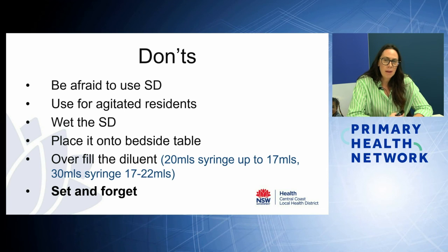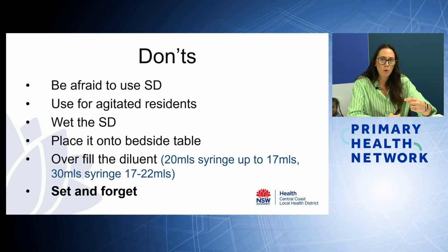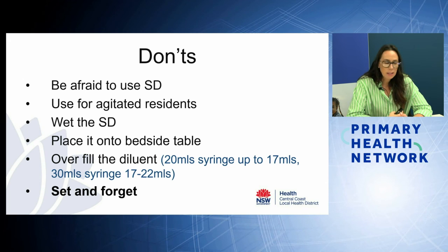The only reason you may need to increase someone to a 30 ml syringe is if they've got lots of symptoms, so they've got lots of medications and a high volume of medicines. So sometimes we do need to have a higher volume. If you need to recalibrate your machine, reach out to MediLogic for that. And don't set and forget. They're not set and forget devices, so make sure you're reviewing them every 4 hours at the minimum.